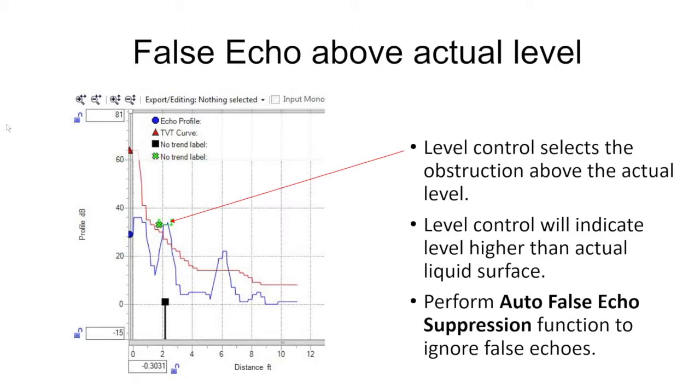In this case it could be a pipe, it could be the bottom of a mounting nozzle, could be anything that reflects the energy above our actual target. Unless we do anything it's always going to select that false echo as our actual level. So what we'll need to do is go into the program and do an auto false echo suppression. The actual procedures vary between the models of level transmitter. You can refer to the manual or give us a call at Gilson Engineering.